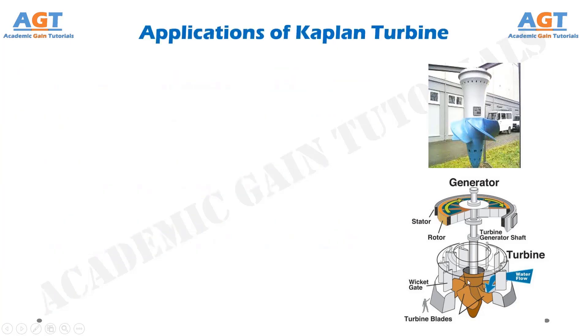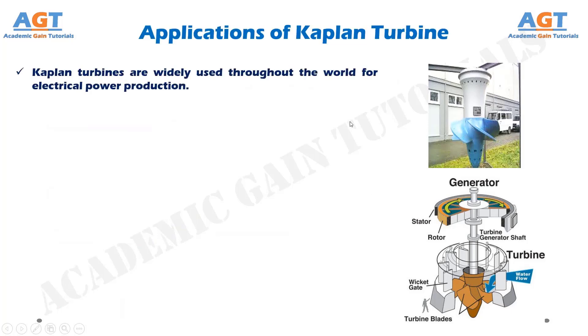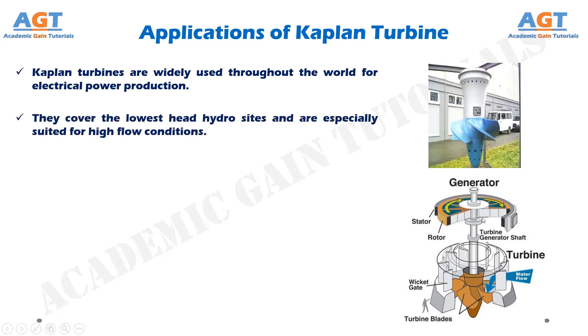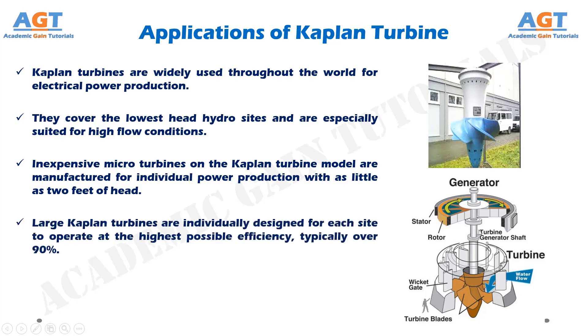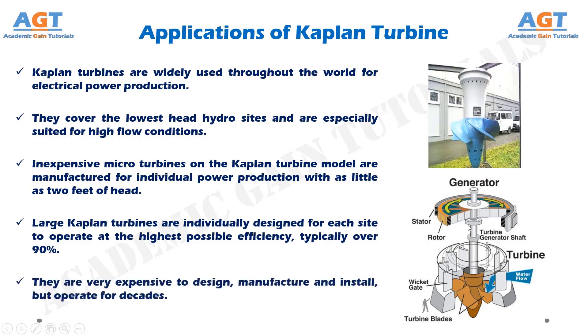Kaplan turbines are widely used throughout the world for electrical power production. They cover the lowest head hydro sites and are especially suited for high flow conditions. Inexpensive micro-turbines on the Kaplan turbine model are manufactured for individual power production with as little as 2 feet of head. Large Kaplan turbines are individually designed for each site to operate at the highest possible efficiency, typically over 90%. They are very expensive to design, manufacture, and install, but operate for decades.